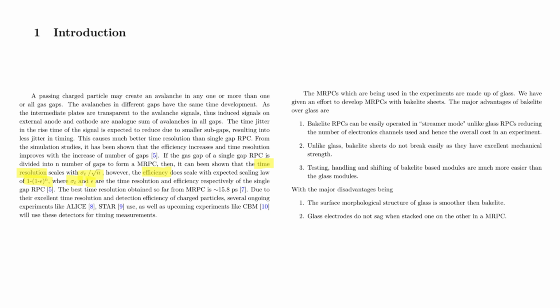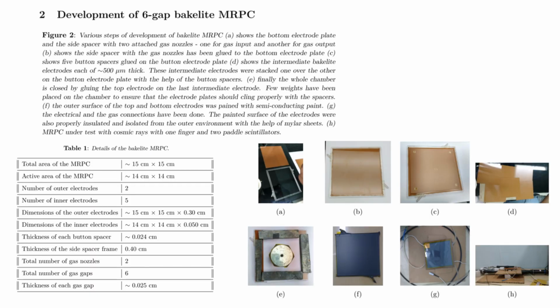The Bakelite MRPC was developed keeping in mind the potential application of MRPCs in medical physics, especially in positron emission tomography. It is a very well-known fact that MRPCs have very poor detection efficiency of photons at their optimized operating voltages for detecting charged particles. It has been observed that the photon detection efficiency of MRPCs increases as their operating voltage is increased. An increase in operating voltage leads to high gas gain mode or streamer mode of operation and reduces the number of electronics modules. Bakelite-based RPCs are very well known to be operated in streamer mode, hence our effort for the development of the Bakelite MRPC.